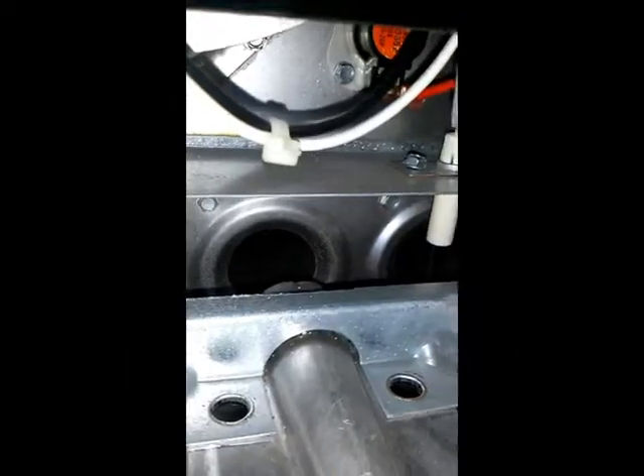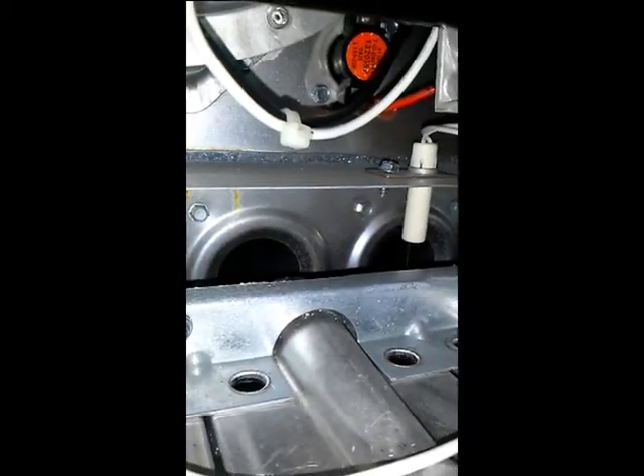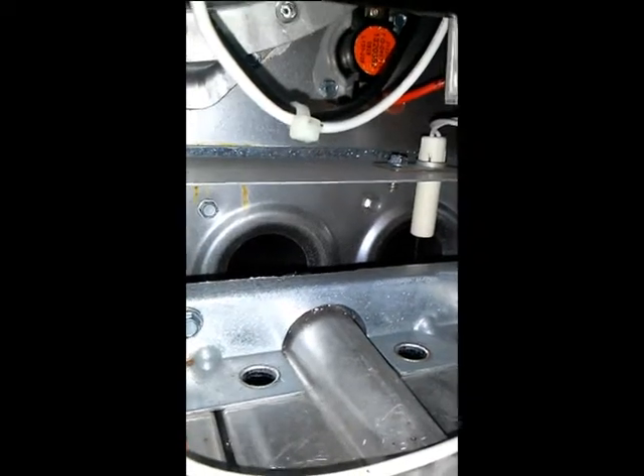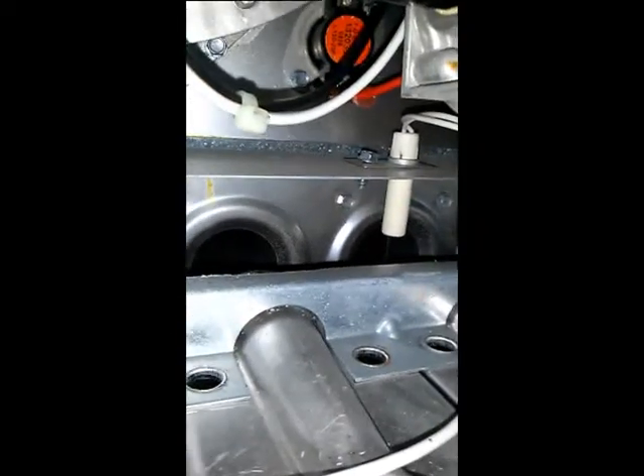So that's one way to check how the heat exchanger is. There's another way too, going through your high limit — you can pull that out, but in this case, because everything is squished in, it's actually pretty difficult to do that. I have done that with this furnace last year, but I couldn't really see anything doing it that way.